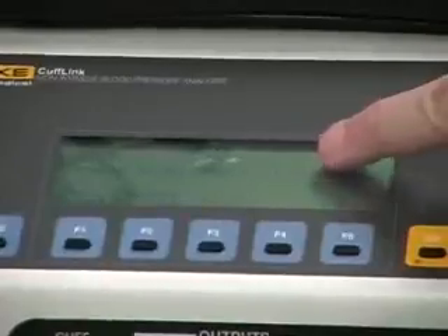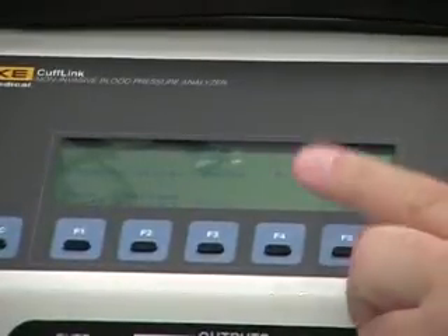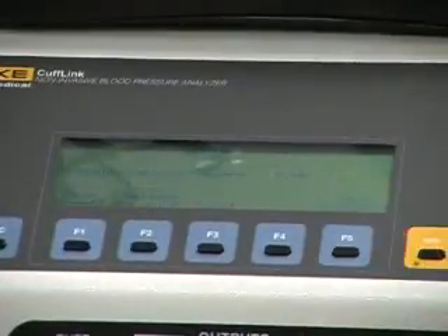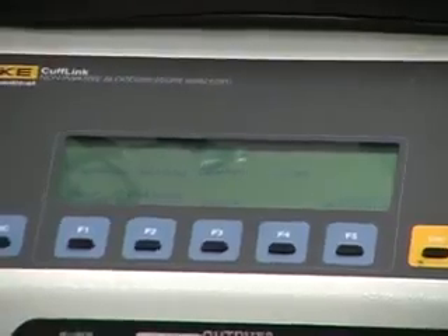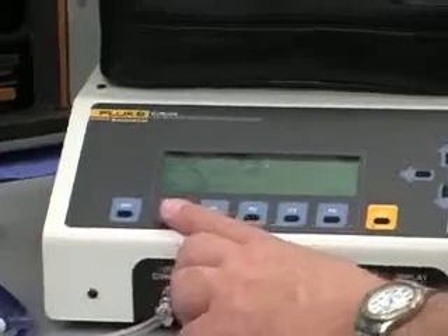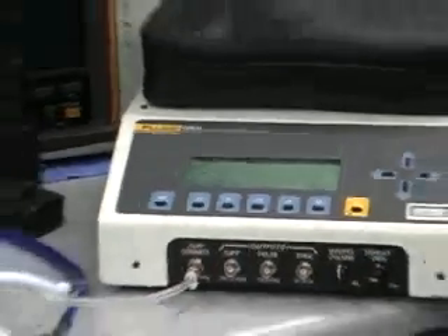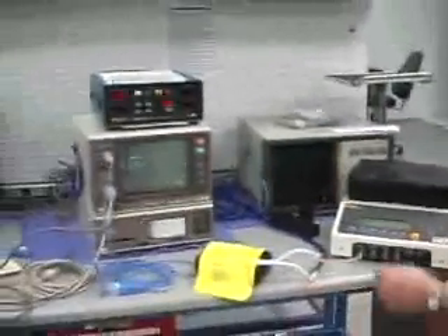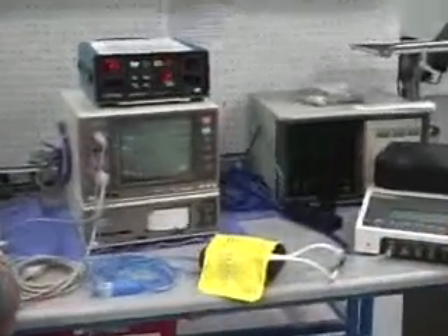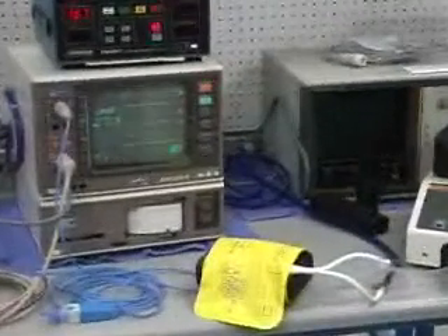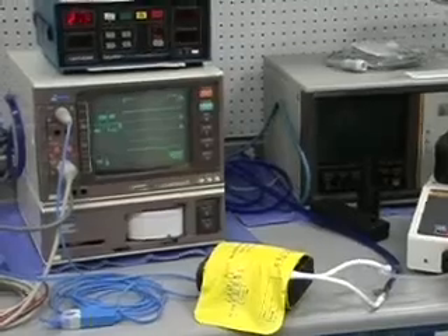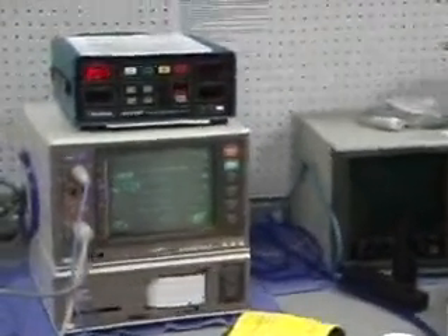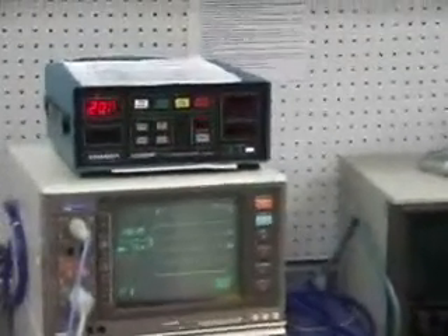We're reading 0.5 millimeter of mercury. And if we wanted to, we can just zero that out for the most accuracy. So now we're reading 0.00. So let's turn the pump on for a little bit. It's inflating the cuff and the other related accessories. Bring it up to a value, let's say around 200. Then let it just dynamically settle.